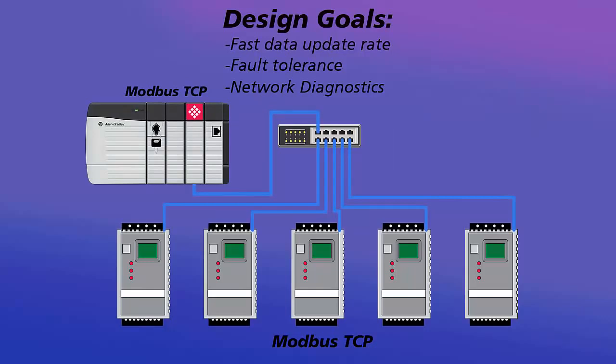A single client has no problem communicating with several different servers on the same network, but there are some considerations using such an arrangement. The client will open communications with each drive one by one, sending a read or write command, and waiting for a response. Once the client receives the response from the server, it will close the connection and move on to the next drive.